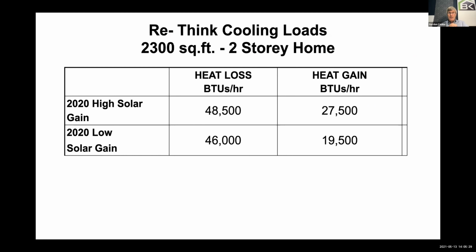And just to give you a sense of a 2-story house, 2,300 square feet, all I did is took a heat loss, heat gain, and changed the solar gain of the windows in that house. The heat loss, of course, hardly changed at all. But the heat gain went from 27,000 BTUs, 2.5 tons, some might say 3 ton, to 19,000 BTUs, which would be, in fact, 2 tons, in fact, 1.5 you could do in this house. Because that's, again, an intermittent load. So imagine what that might do for you.